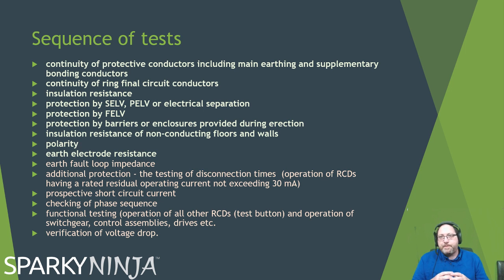The live system tests are fault loop, additional protection with RCDs, prospective short circuit current, checking of phase sequences, functional testing and voltage drop. Again, you'll do the earth fault loop test. You'll then probably do the loop test and the prospective fault current near enough at the same time. That's what I do. But then you'll do the RCD tests, and then you do your functional. So whilst the list is long, hopefully your assessor will introduce you to the assessment. You'll go, oh no, we're just going to do these 7 or 8, whatever it is. Okay, but the ones that you do, you must do in this sequence.